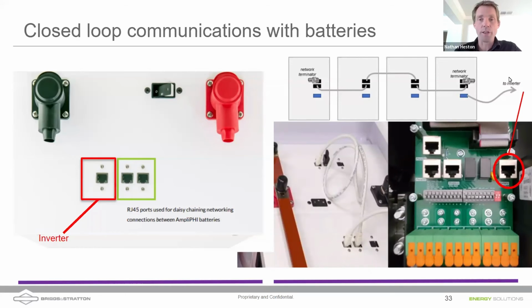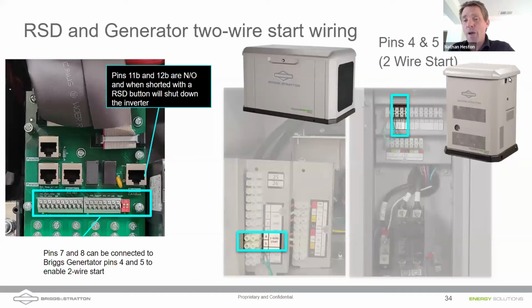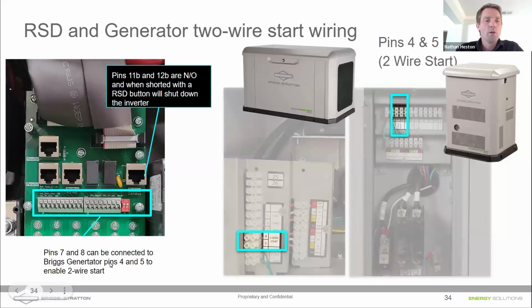Now, I do point out that on our 6.6 batteries, all of the communications, all of the power connections for each of those modules, those 3 modules that stack on top of each other, all of that's done through that rapid stack technology, in which it's simply a stacked up electrical connection. I don't think there's time really to go through all of the communications pins that are here, but I do highlight that pins 7 and 8 can be used for that 2-wire start if you're integrating this with a generator.